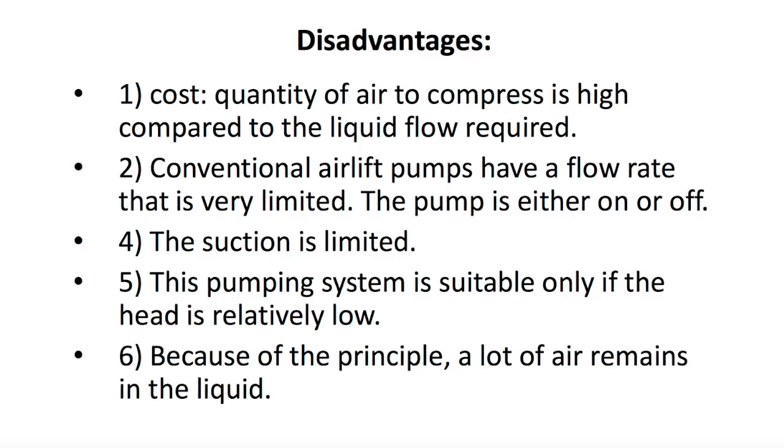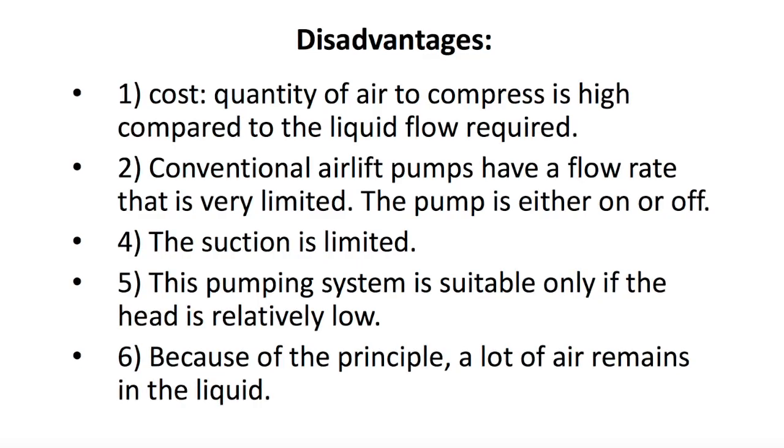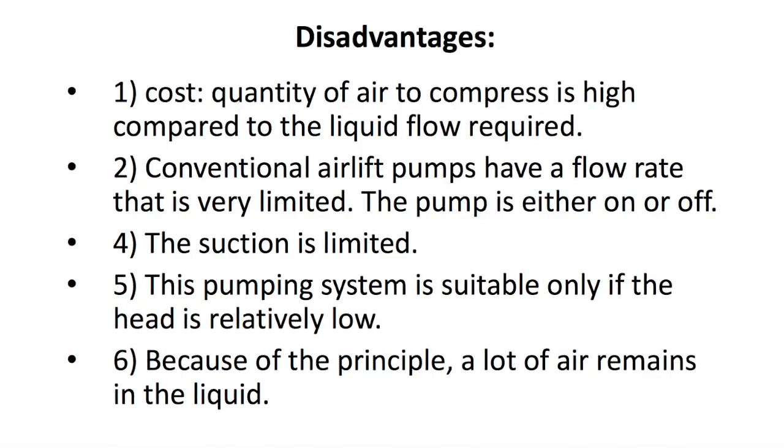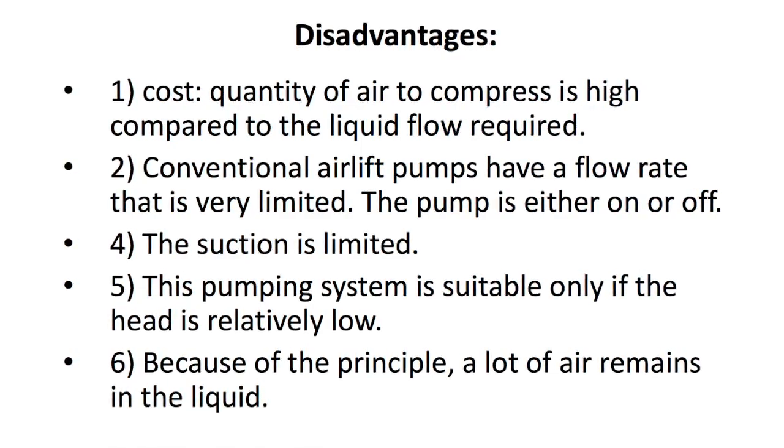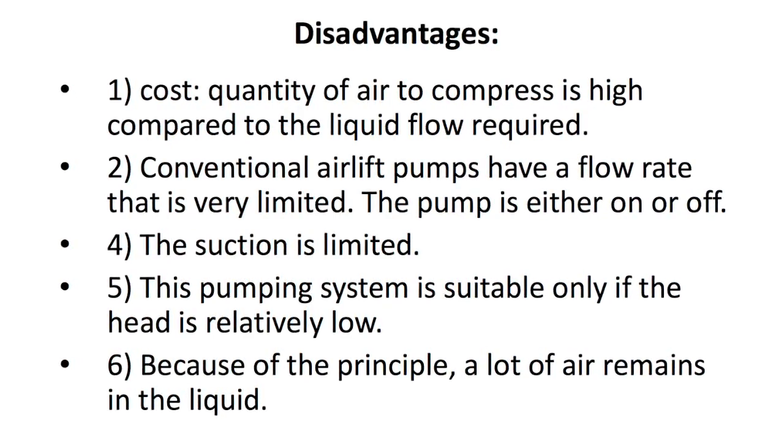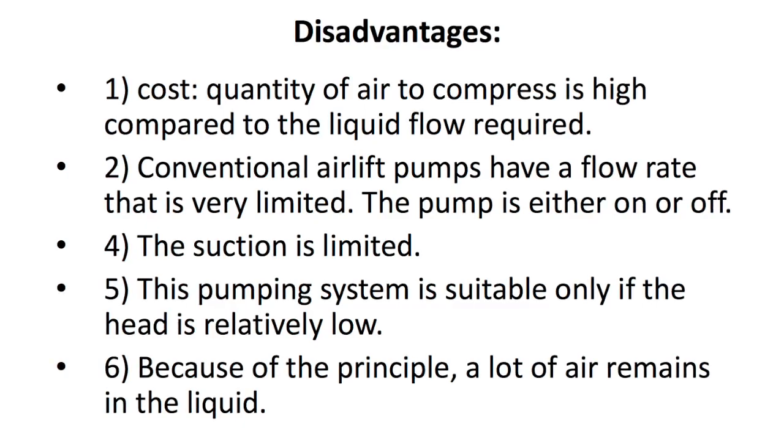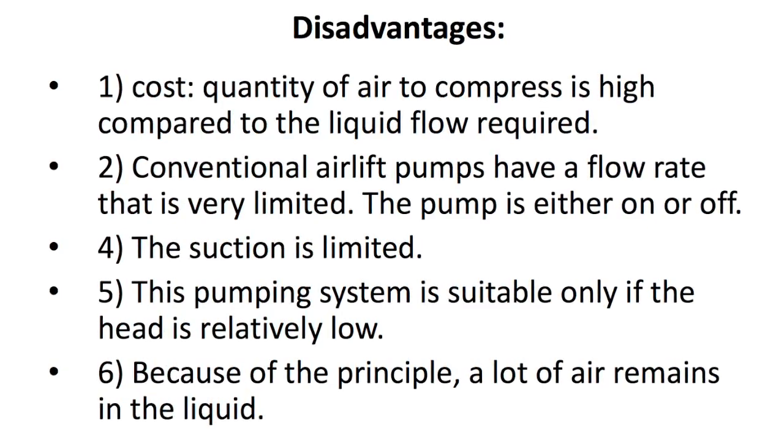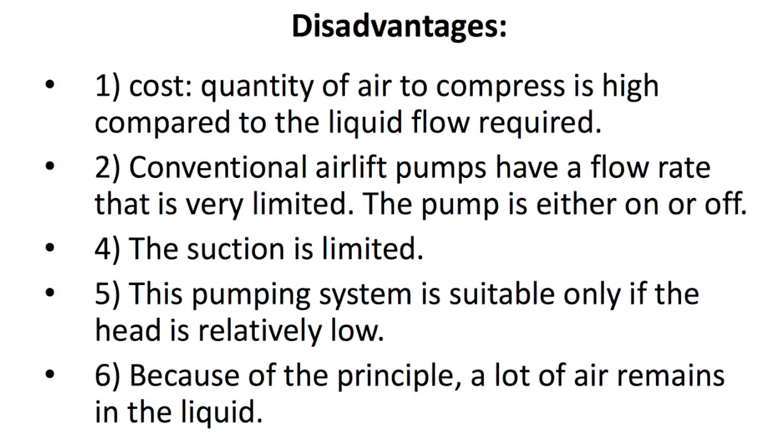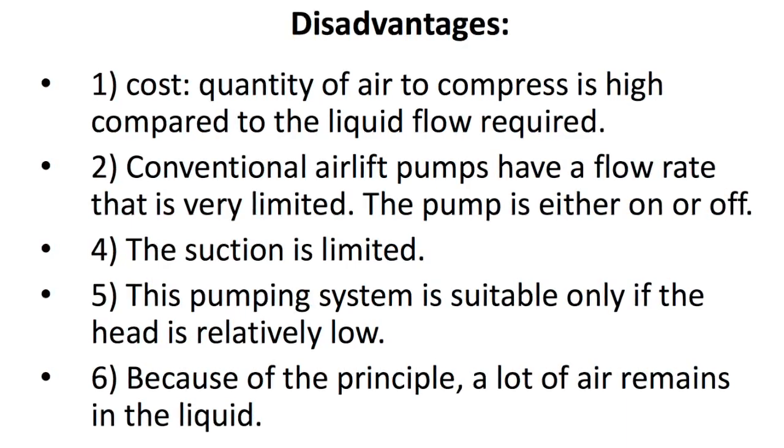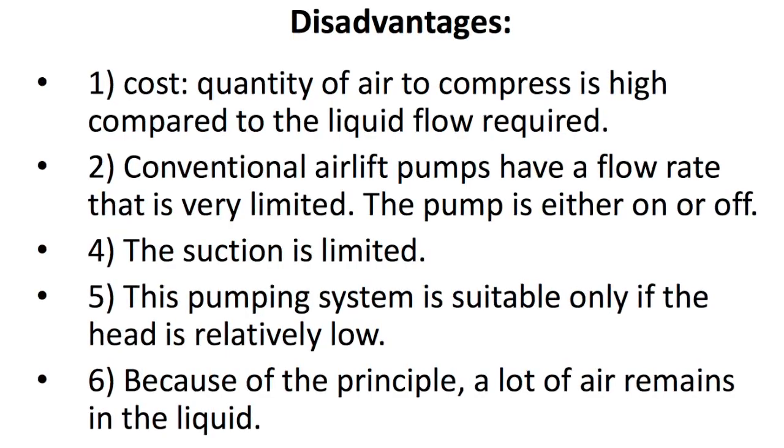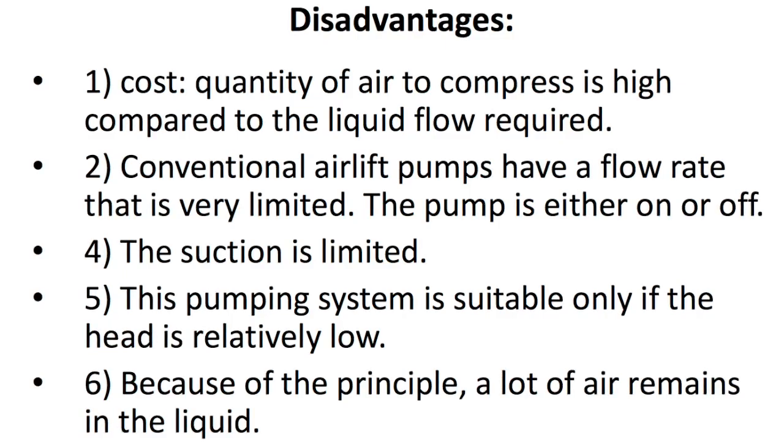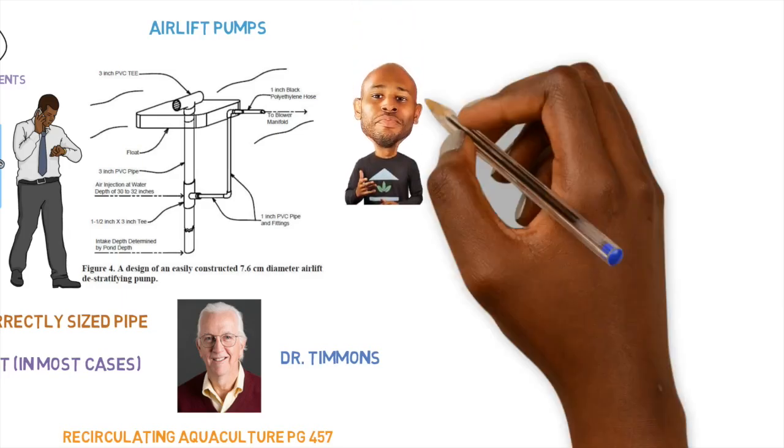And the disadvantages goes as follows. One, cost. Quantity of the air to compress is high compared to the liquid flow required. Two, conventional air lift pumps have a flow rate that is very limited. The pump is either on or off. Four, the suction is limited. Five, this pumping system is suitable only if the head is relatively low. This means that you cannot pump these things super high in the air. Six, because of the principle, a lot of air remains in the liquid.